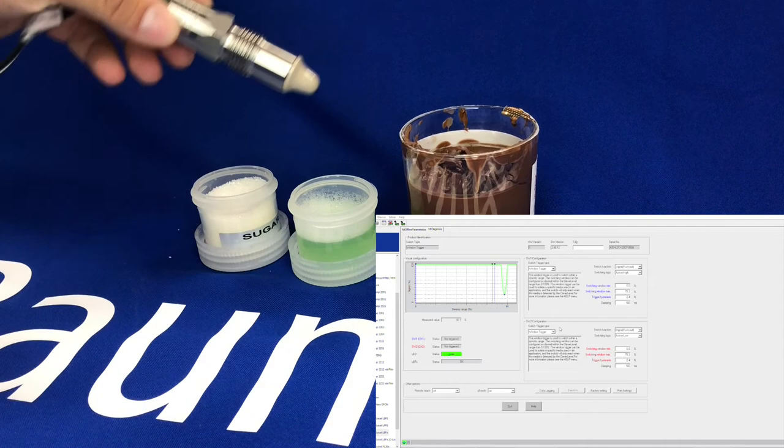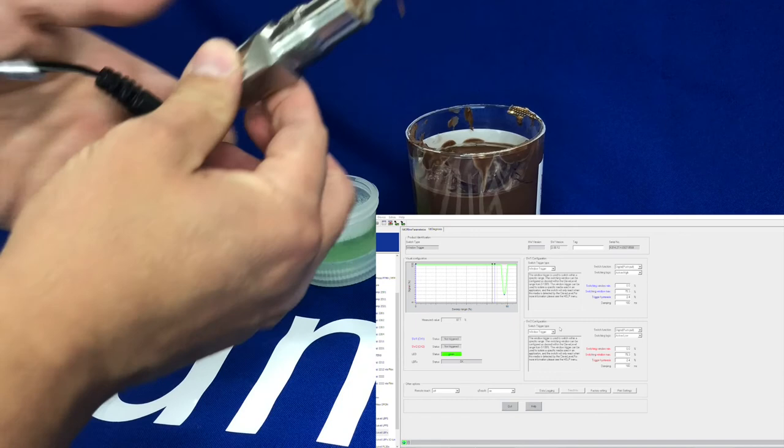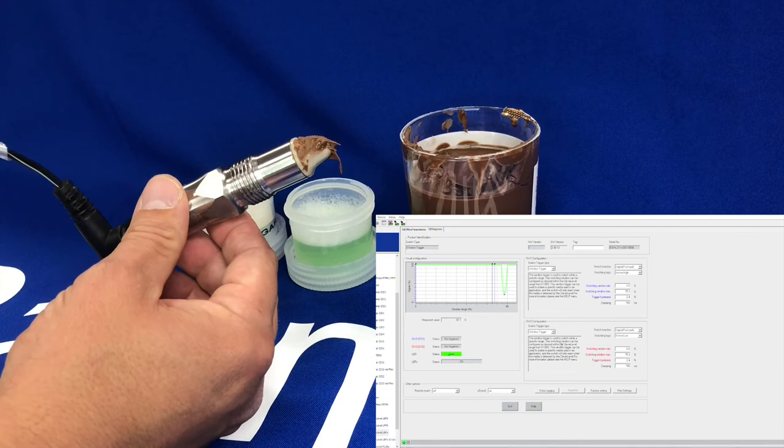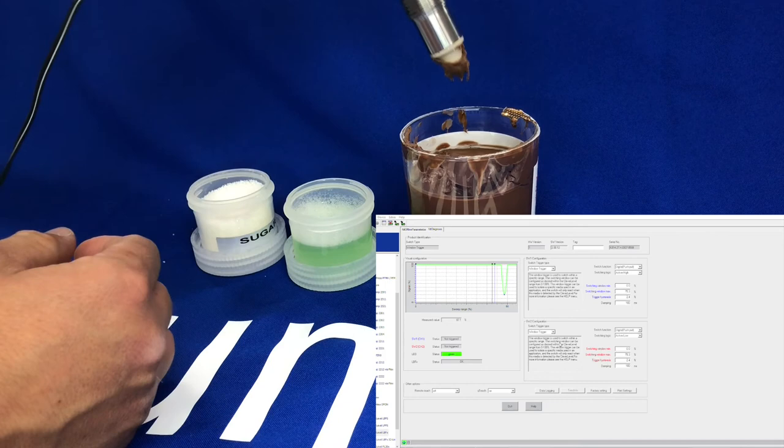This is the status that we want to ignore. If we wanted to ignore this scenario where there's a build-up of sticky media on the tip, we'd do this. If it was foamy, we'd put some foam on the tip. That's saying what we want to ignore. Now it's saying fill the tank.